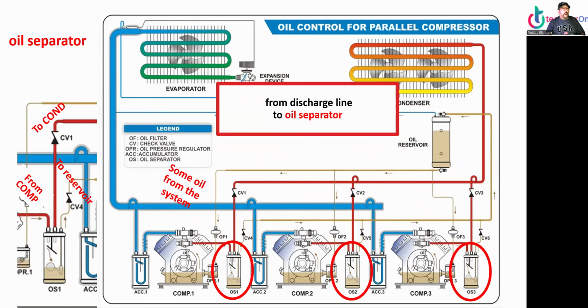All right, now from the discharge line to the oil separator, first oil comes in. Follow the arrow. System oil comes from the system. It goes from the discharge line into the oil separator.